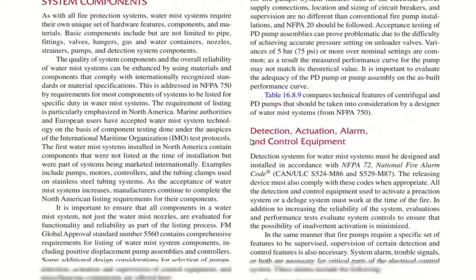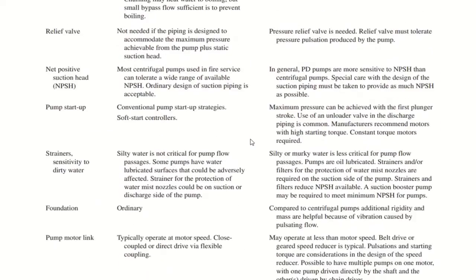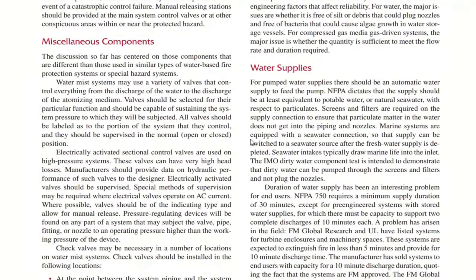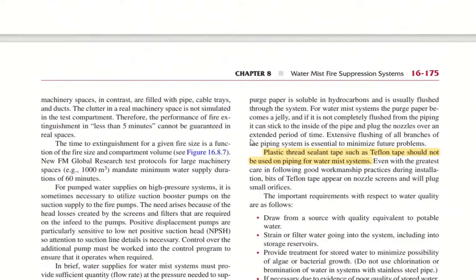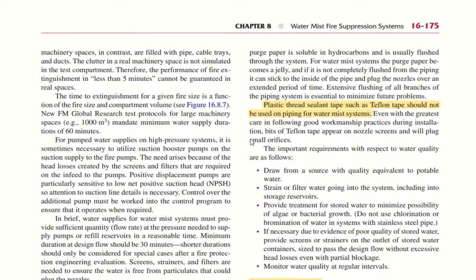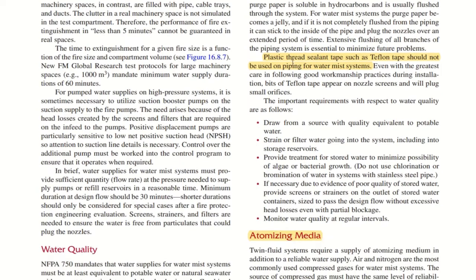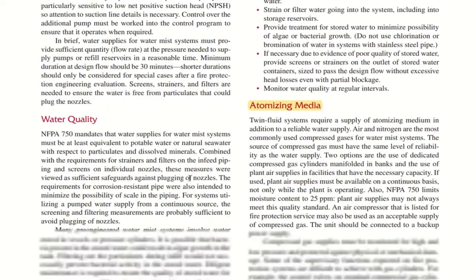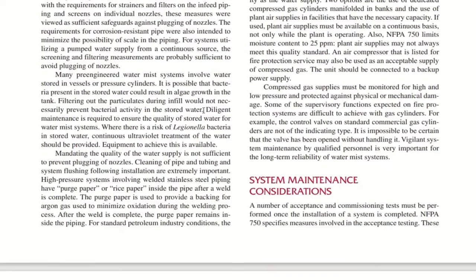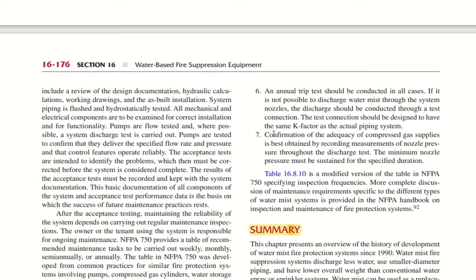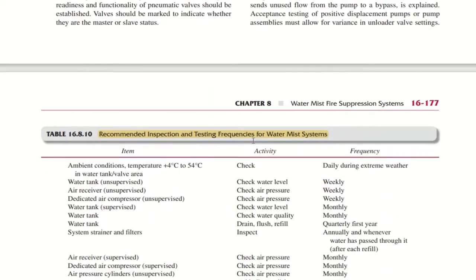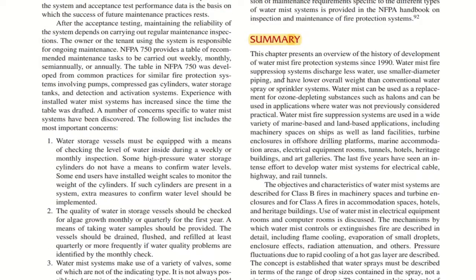You have various things to go through. Since this is a big and unique topic, you might expect a question on water mist fire suppression systems in the examination. Plastic threaded sealant tape such as Teflon tape should not be used on piping for water mist systems. You have atomizing media. So system maintenance considerations. So basically this is covering everything from A to Z of water mist fire suppression systems. The summary itself is so big, we will just go through a few points.